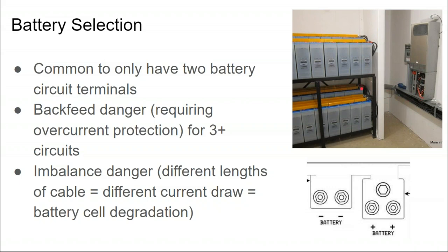These battery circuits have been carefully cut and selected so that these home runs are the same length, because at such high amperage, a difference in length in your battery cables can result in one battery being used more heavily than the other. That will cause the heavier-used battery bank to fail earlier than it should, dragging down the rest of the battery bank with it. So the more uniformity in the system, the better.